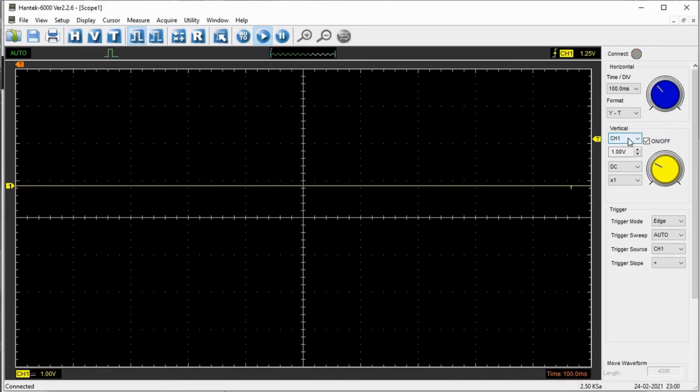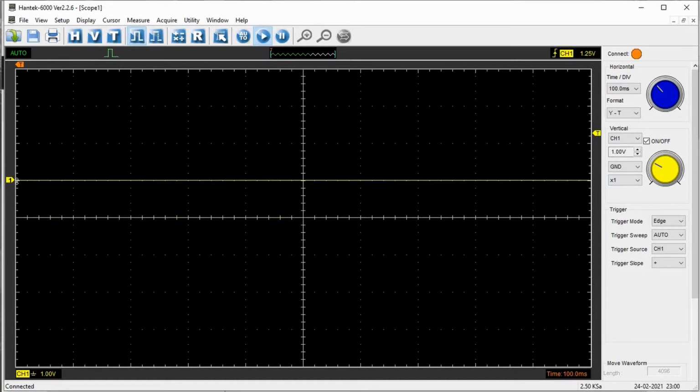The second thing that you have to do here is, for this channel 1, the measurement mode: first make it ground and move this point to where you want the ground reference. What it means here is that the waveform will start from this 0 voltage point. You can either go above this or come below this. So you should always know the baseline, that is the 0 line from which the measurements are done. It is also specified by this channel 1 baseline, which is already showing here.